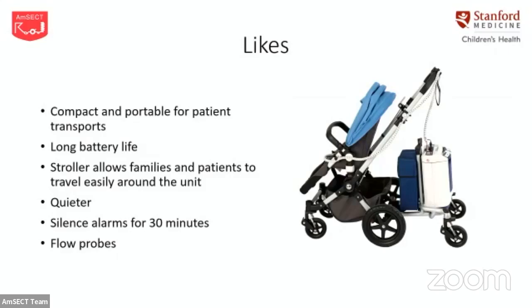The silence alarm button for 30 minutes is really nice as well. Typically, I've had temperature alarms go off. Let's say we're in the cath lab and the patient's draped and covered, and you get a high temperature alarm for that flow sensor. So you can just silence it, because obviously I can't undrape the patient at this moment and fix that alarm.